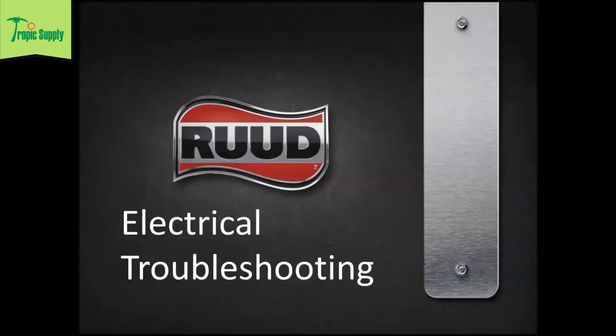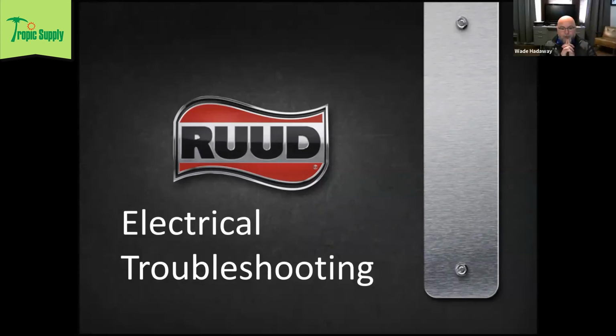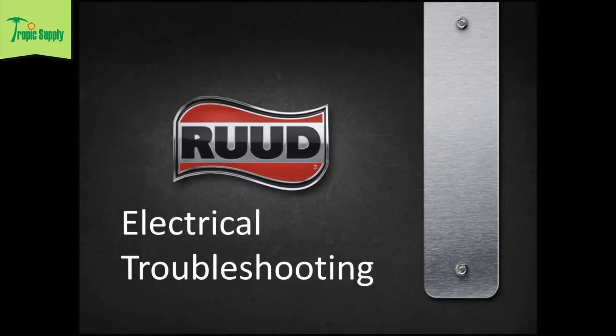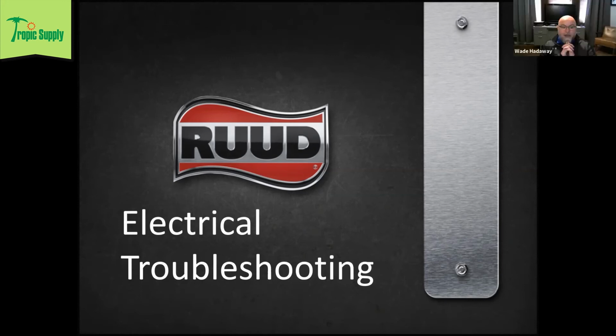Wade, yeah, two questions. Why does my contactor relay after the machine is off make a noise, like is 24 volts excited? There could be a voltage issue happening there. I'm not sure if he means a contactor chatter. Yeah, I think that's my interpretation. So if your contactor's chattering at any point, that means that your coil's not creating the electromagnetic field that it needs to pull that contactor in and hold it down.